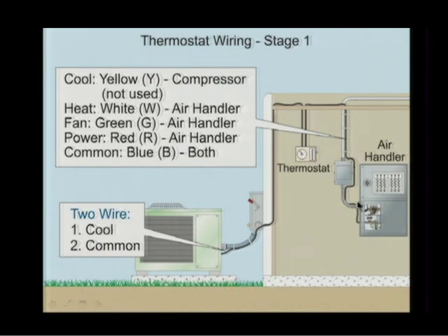So what do we have? I have a yellow for cool. I have green at the thermostat for fan. I have white at the thermostat for heat. I have the common conductors not making a termination at the thermostat, but all common conductors go over to the transformer common terminal. Then I need to have power to the thermostat. I leave the transformer secondary, and I run a red wire to supply the thermostat.